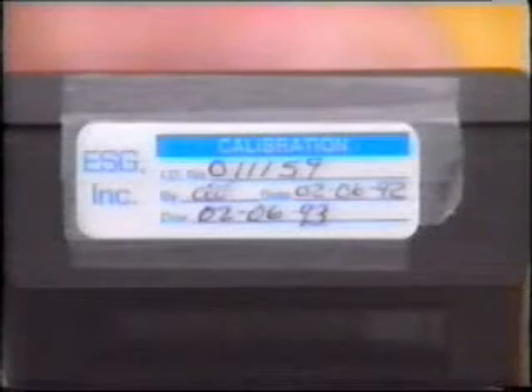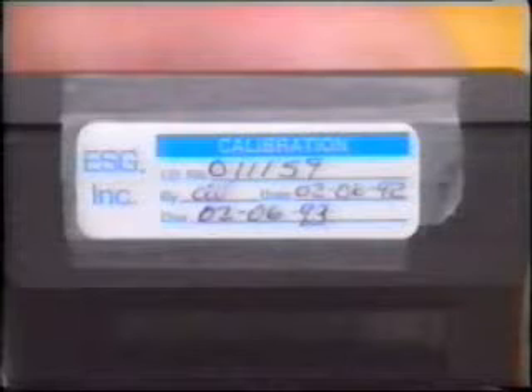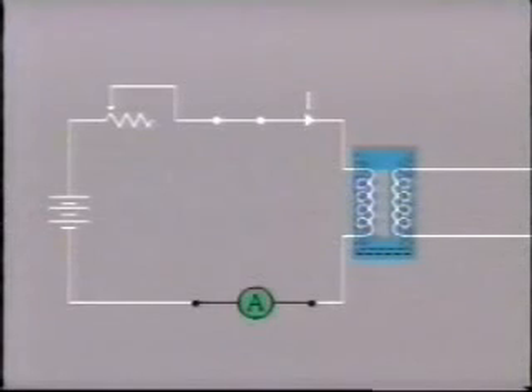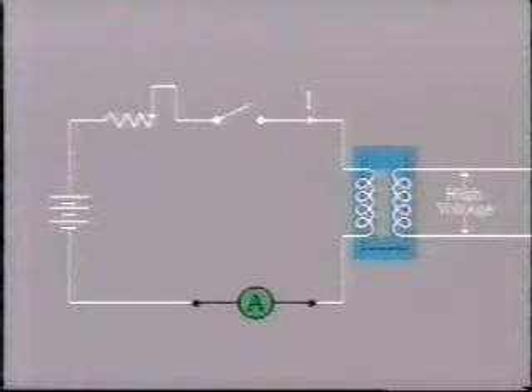Also, make sure that your multimeter is routinely calibrated. If you are measuring DC current in an inductive circuit, remember to reduce the voltage before interrupting the current flow at the end of the test. Otherwise, a large voltage may be induced into the circuit, causing damage to instruments and perhaps shock to personnel.